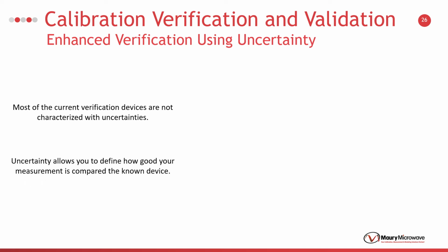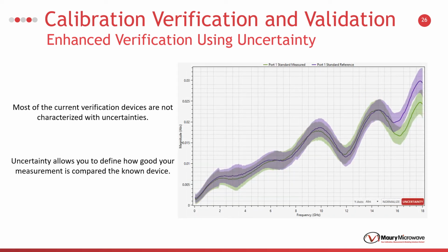There are two conditions to decide if a calibration was successful. The first is if the setup has low uncertainty, and secondly, if both of the measurements, the reference and the recent measurement, have a similar uncertainty trend. Then this can be considered an excellent calibration. In this example, there is an obvious separation between the uncertainty trends above 15 GHz. Therefore, we can consider this a bad calibration.